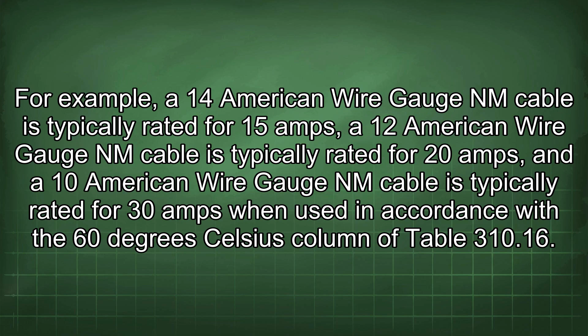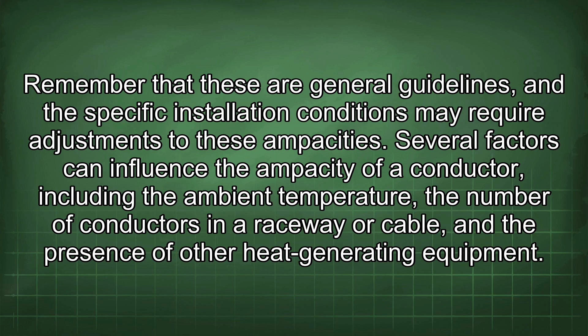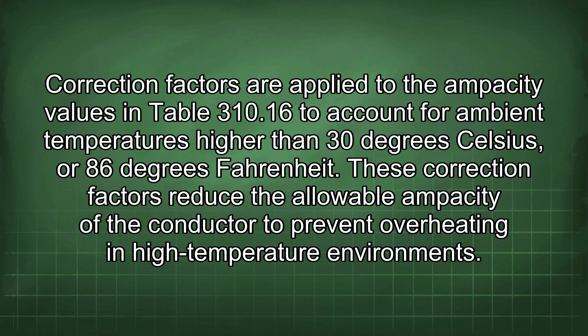Several factors can influence the ampacity of a conductor, including the ambient temperature, the number of conductors in a raceway or cable, and the presence of other heat-generating equipment. Correction factors are applied to the ampacity values in Table 310.16 to account for ambient temperatures higher than 30 degrees Celsius or 86 degrees Fahrenheit. These correction factors reduce the allowable ampacity of the conductor to prevent overheating in high-temperature environments.